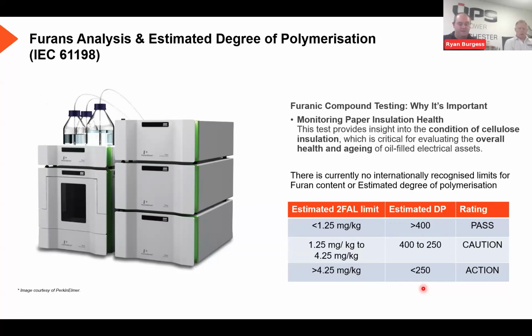Yeah, so we put a value of 250 on there. That's the value we use at VPS. I mean, it's a conservative estimate. Probably 150 is closer to the mark, although when it gets to that level, the transformer can still operate normally for many years. But if it's exposed to external events like lightning strikes or mechanical shock, it has a higher risk of failing.